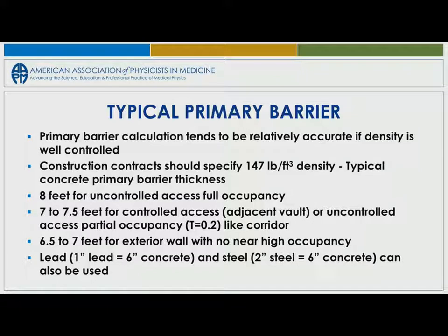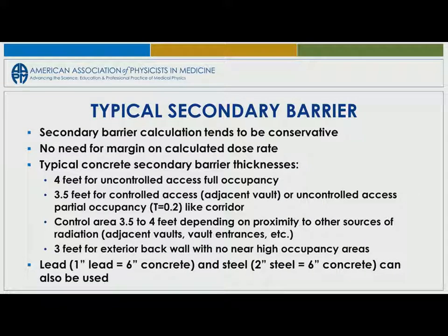And for conversions, roughly 1 inch of lead equals 6 inches of concrete, and 2 inches of steel equals 6 inches of concrete. Your typical secondary barrier, you don't really need a fudge factor. They tend to be, quote, conservative. So if you do them out of NCRP 151, your secondary barriers will be fine with no other conservative factors applied to it. You don't really need a margin on those.